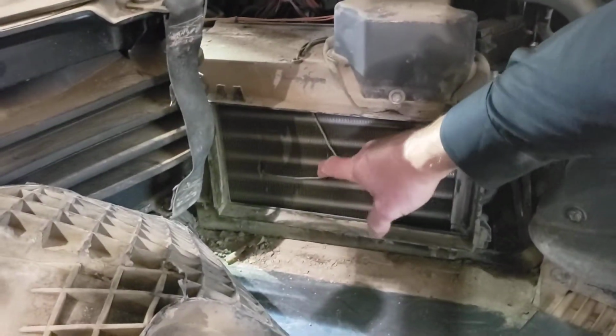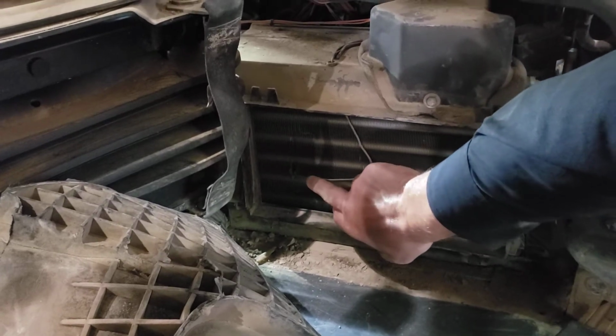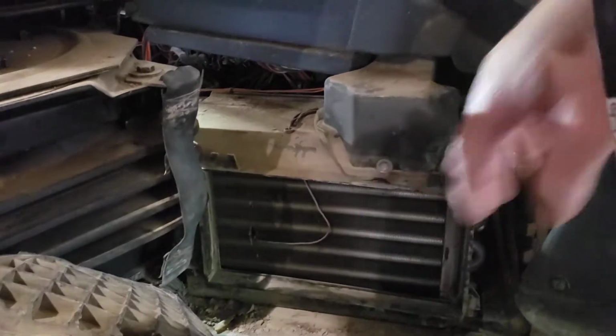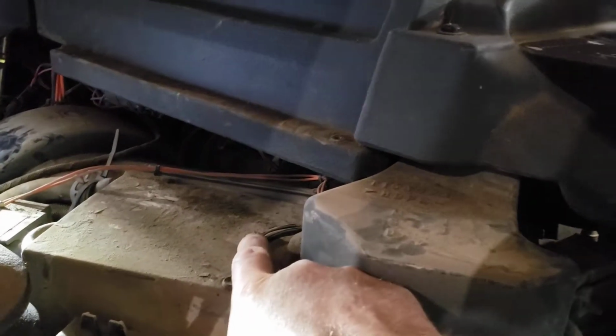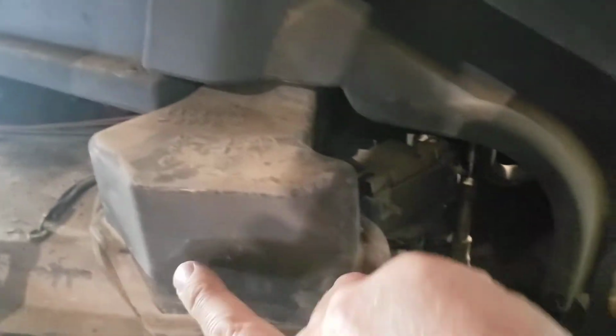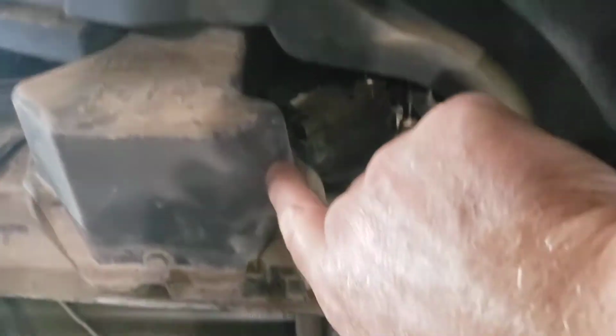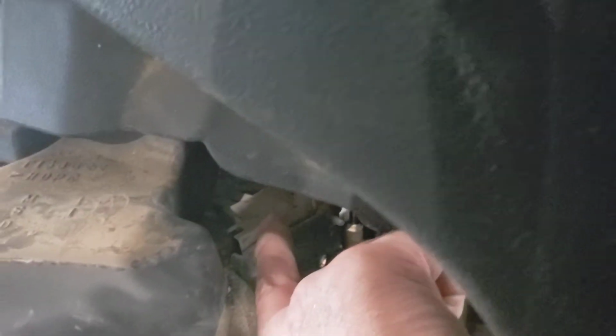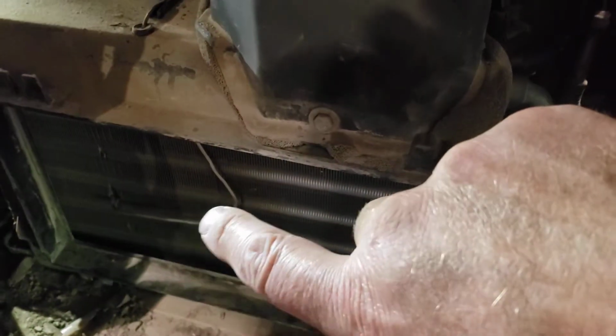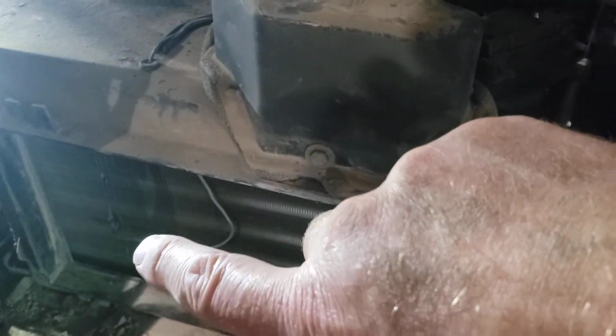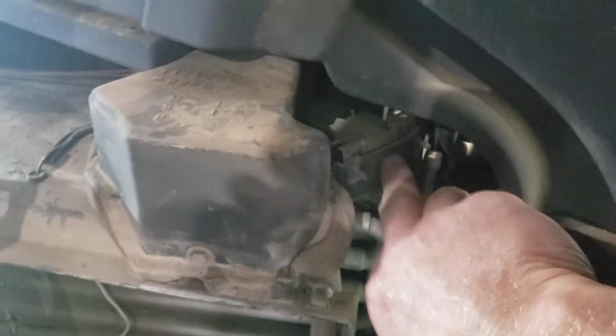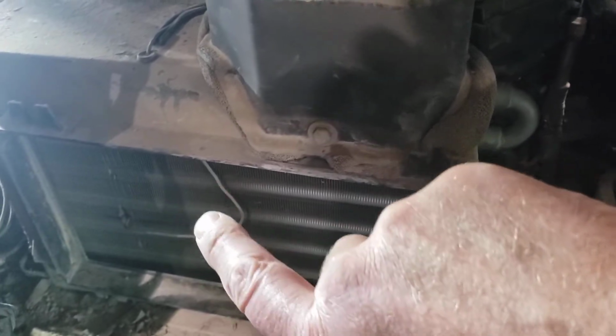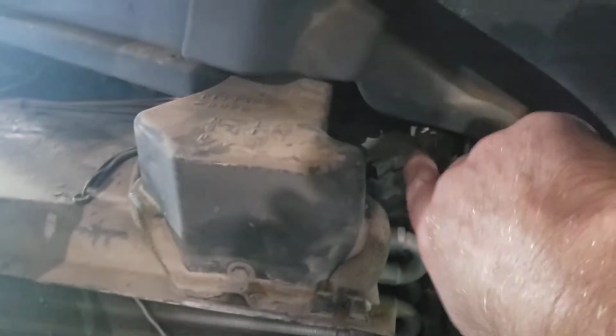And then we've got a capillary tube stuck in the fins here, I see. If I follow that capillary tube up, I find it runs around, kind of sitting in a channel here, protected. It goes around behind this box, which is part of the air handling system. And then over here, there's a thermostatic switch. So even though this is an expansion valve system, we've got our H-block expansion valve. When I saw this, I thought, oh, maybe it's got a right angle expansion valve. But no, this is the capillary that goes into a thermostatic switch. So they call this a freeze switch or a thermostatic switch.